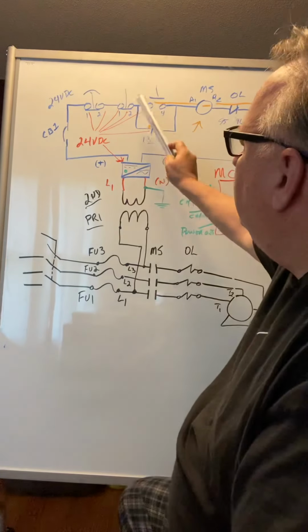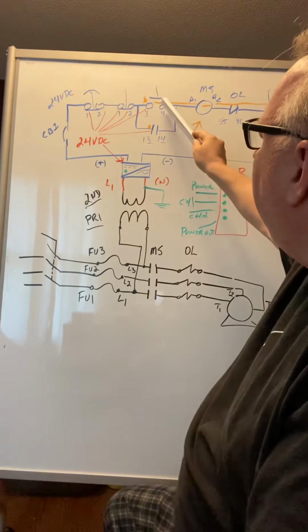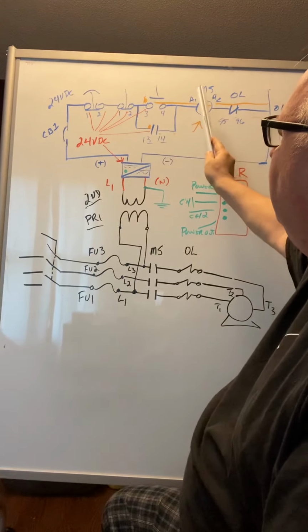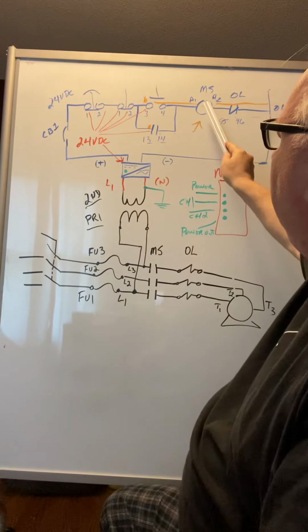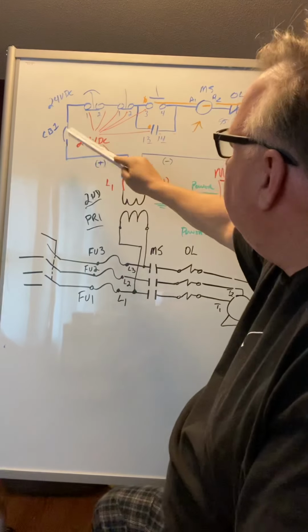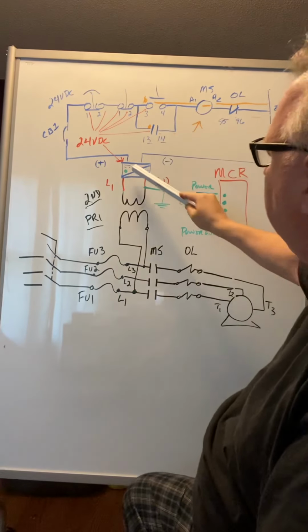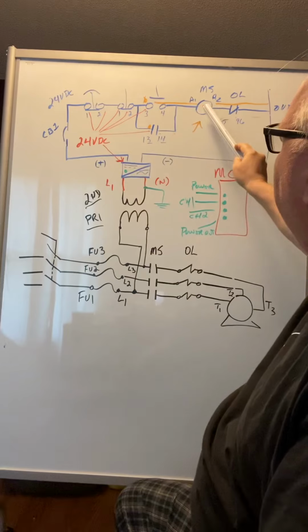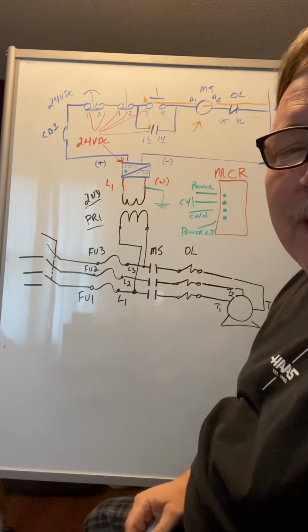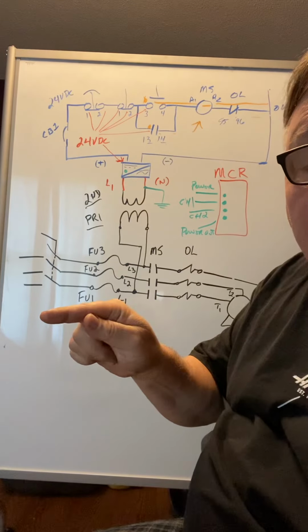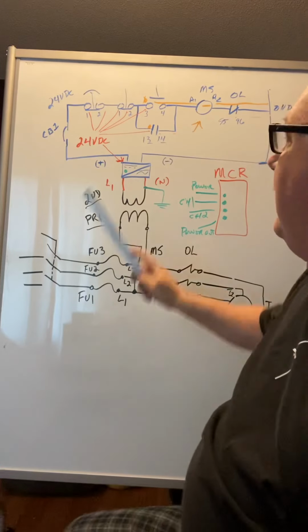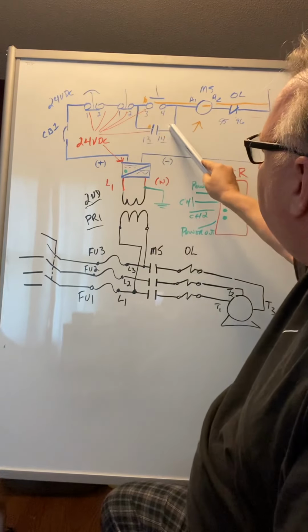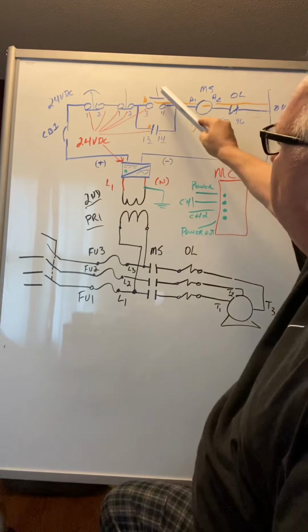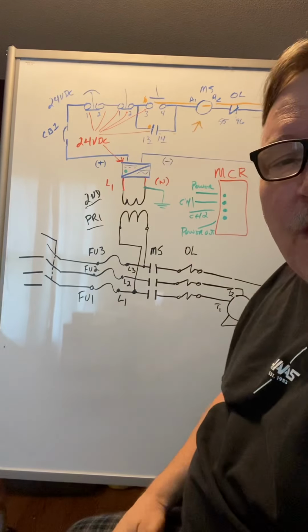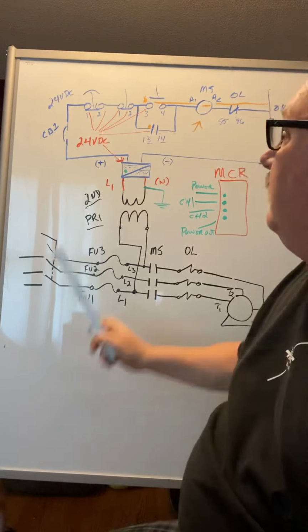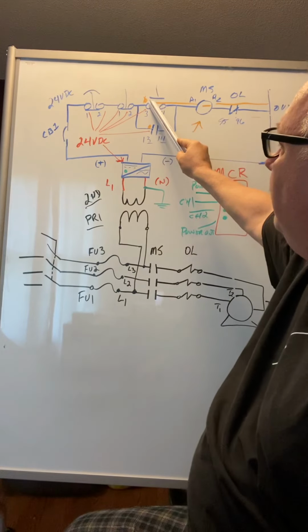Okay? So if your operator says, I push my button and nothing happens, you come over, you've checked the e-stop, you've checked your circuit breakers, you've checked your 4 green lights, you checked your power supply, you got your green status light there, you manually push that motor starter in and it turns on and it stays on. That's telling you that you've got your latch right here, okay? But your push button switch is your problem where you want to start your look. You're going to start to see if you have power here at 24 volts.